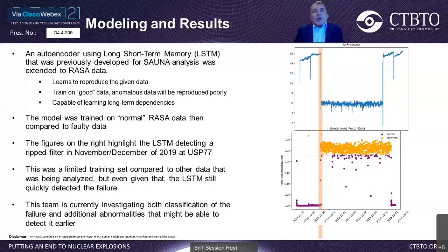We did some work using data science techniques for SAUNA, and we took one of those techniques, known as long short-term memory, and moved it over to RASA data and did some testing. We found that by using just a limited training set, we were able to easily move that model over, and it quickly detected a failure. In this case, it was a ripped filter on a RASA. It was nice to see that it worked well.